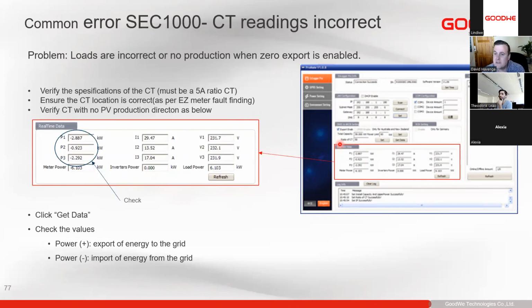It's always best to do this with the inverters not powered on. All the inverters can be powered on, just no AC connected to them. So we put on the DC for our inverters. Inverters are on, they're running, they're powered up, but there's no AC connection to them. We leave the breakers or the AC switch off. So we can check our CTs.